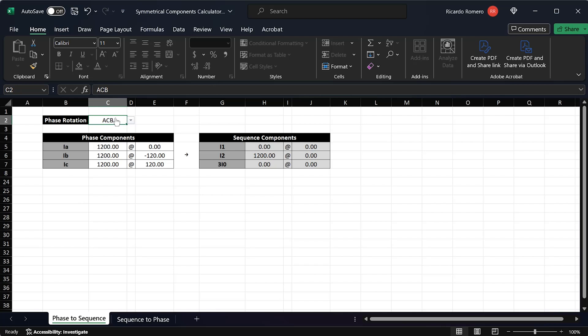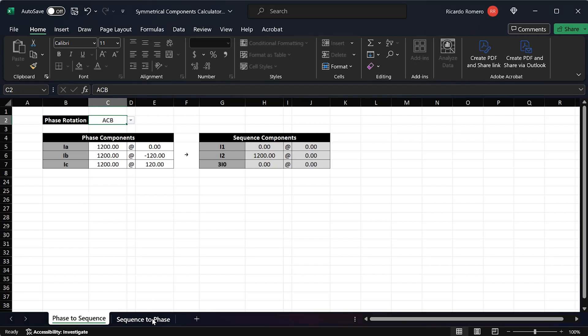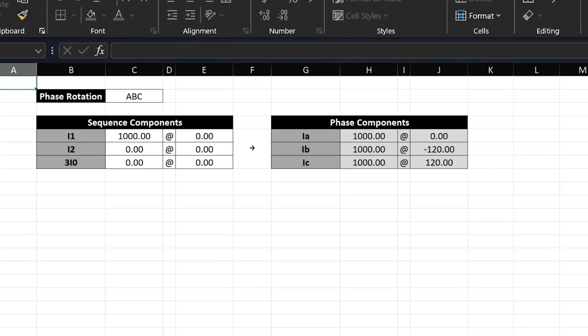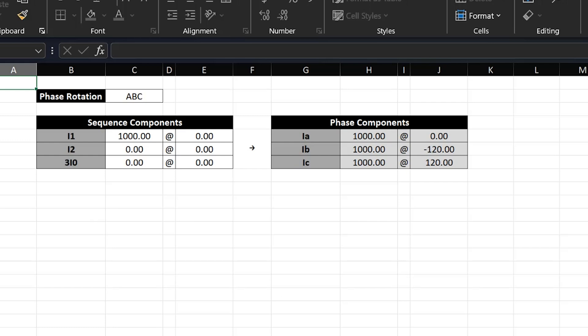Make sure you enter the phase rotation correctly for your system when using this calculator. There is also a tab for converting from sequence components to phase components. For example, if we know we have purely positive sequence current for a certain scenario, we would expect the A, B, and C currents to be balanced with a rotation matching the system rotation. If I have purely positive sequence at 1000 amps at zero degrees and a phase rotation of ABC, you can see that the A, B, and C currents have the same magnitude and are balanced with an ABC rotation.